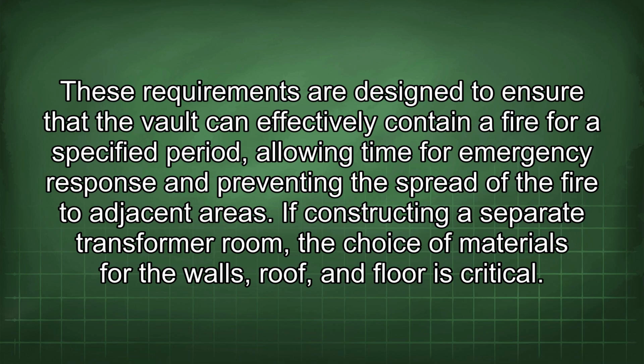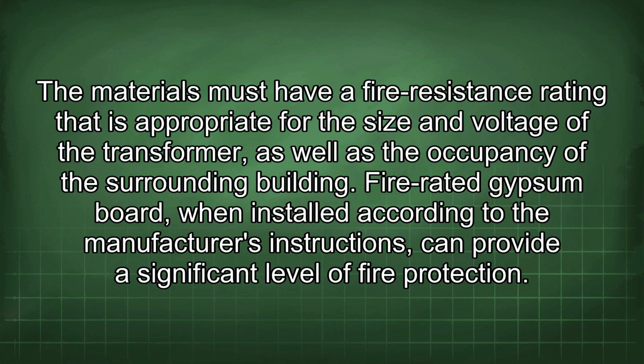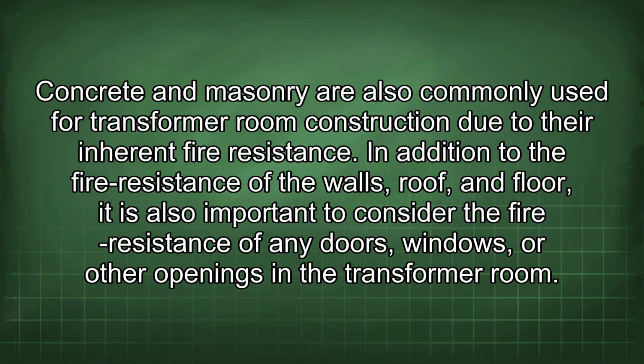If constructing a separate transformer room, the choice of materials for the walls, roof, and floor is critical. The materials must have a fire resistance rating that is appropriate for the size and voltage of the transformer, as well as the occupancy of the surrounding building. Fire-rated gypsum board, when installed according to the manufacturer's instructions, can provide a significant level of fire protection. Concrete and masonry are also commonly used for transformer room construction due to their inherent fire resistance.